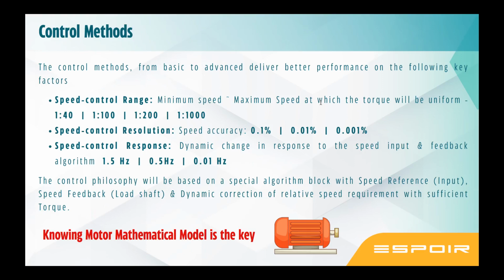The main difference between servo drive and AC drive is almost the same. The game changes because of the motor, because they are permanent magnet, high precision motors. And the drive has many built-in functions, built-in encoder, very high resolution encoders. You have a 1 million pulse per revolution encoder, which is a different technology altogether. Now the market encoders, a standard encoder you get is like, say, 10,000 pulse per revolution at maximum. In servo, you get 1 million PPR, 23-bit, 21-bit, 17-bit, 16-bit, 13-bit. These are all the popular encoder specs which you get in the servo system.